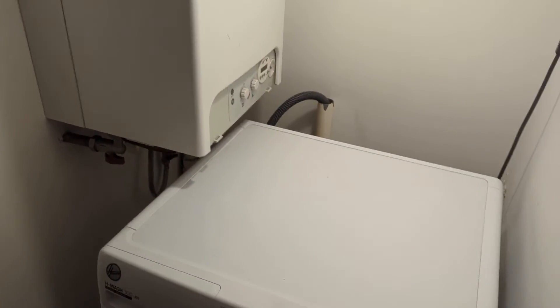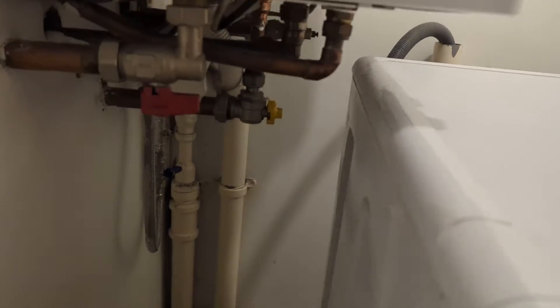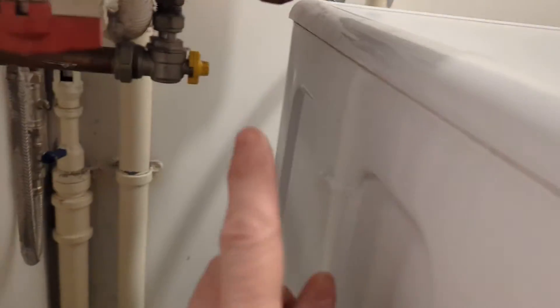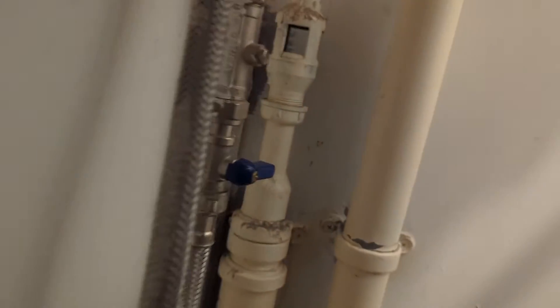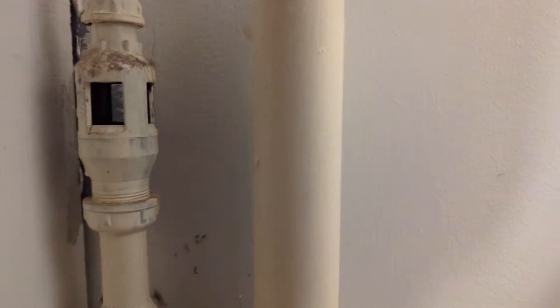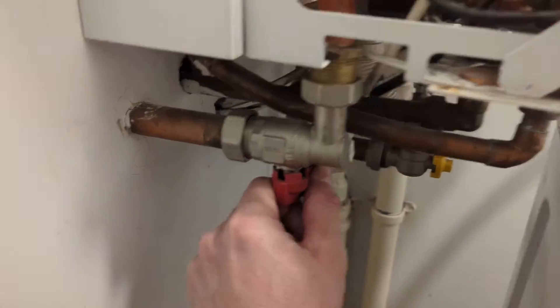Hello customers, fellow gas engineers. I'm here at a Ferroli Optimax 25c. We have a pressure relief valve that's passing — that's the pressure relief valve pipe, which goes into this tundish, and we've got a bit of water dripping through the tundish.